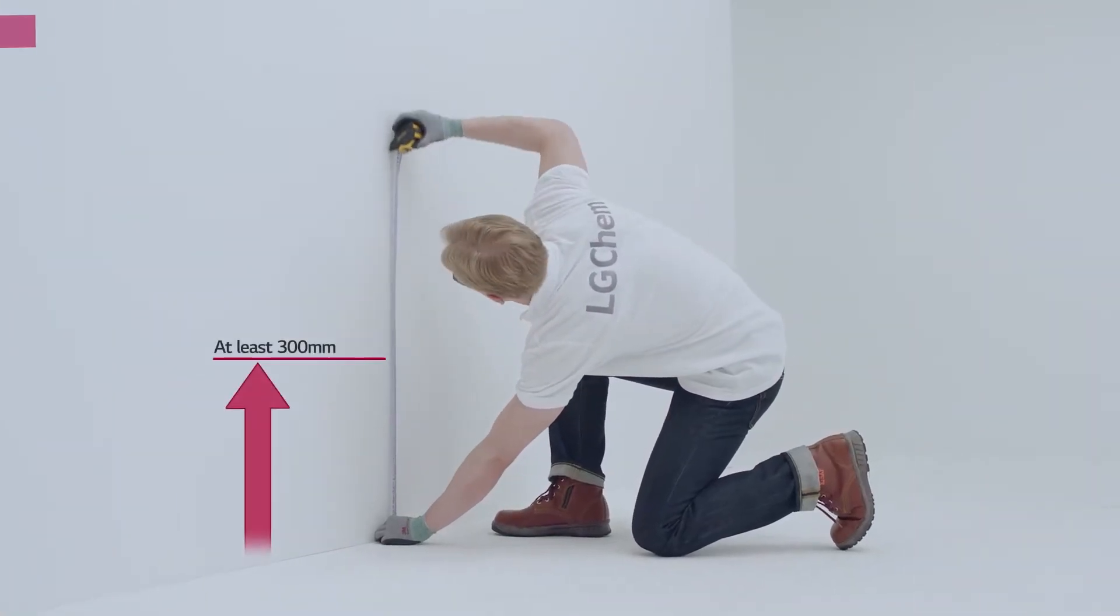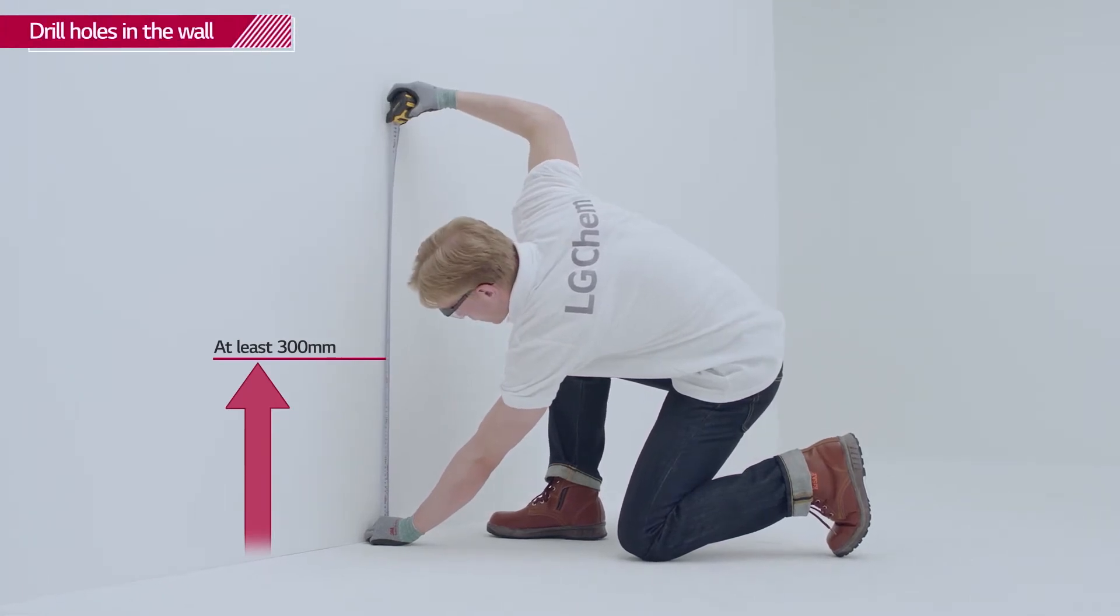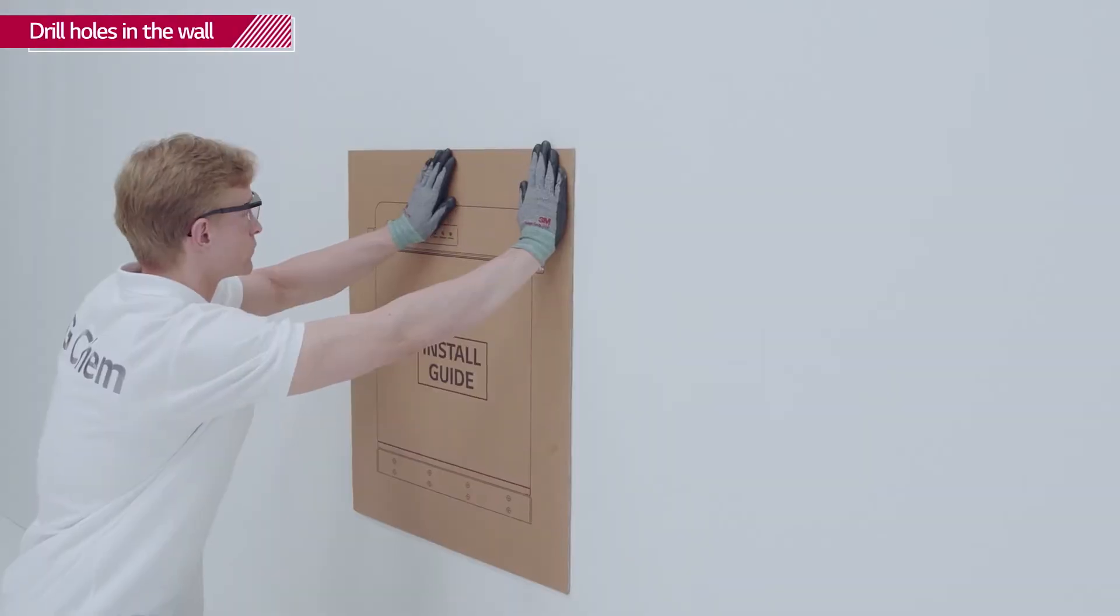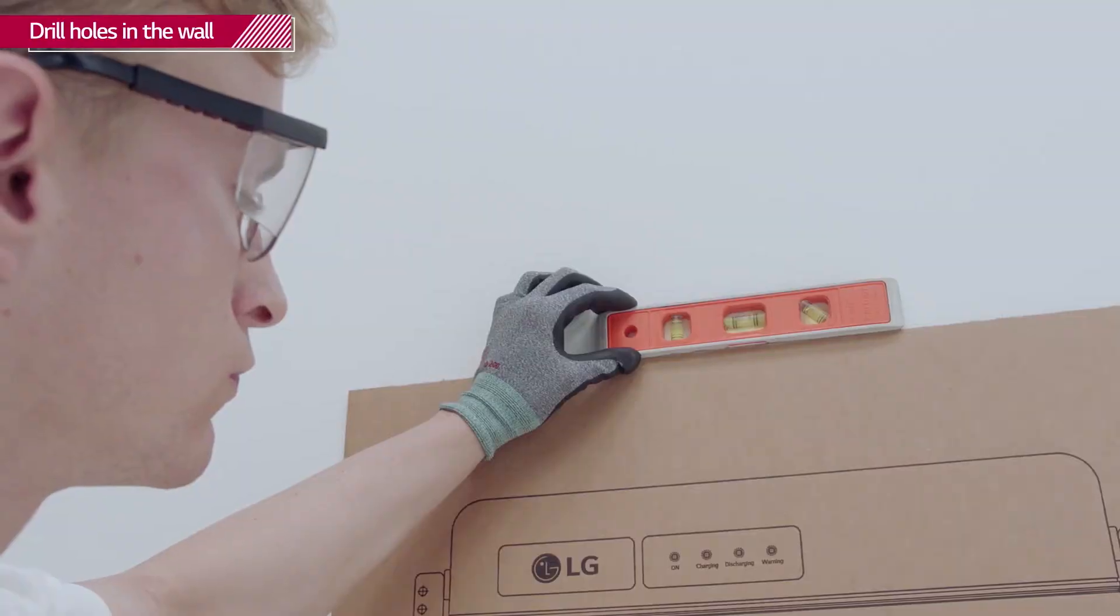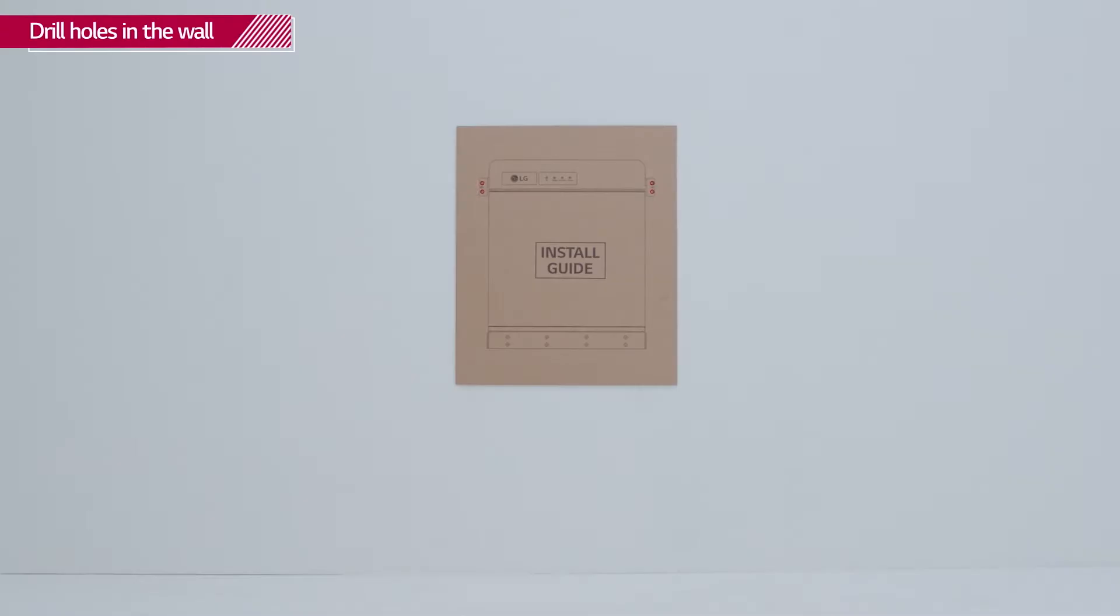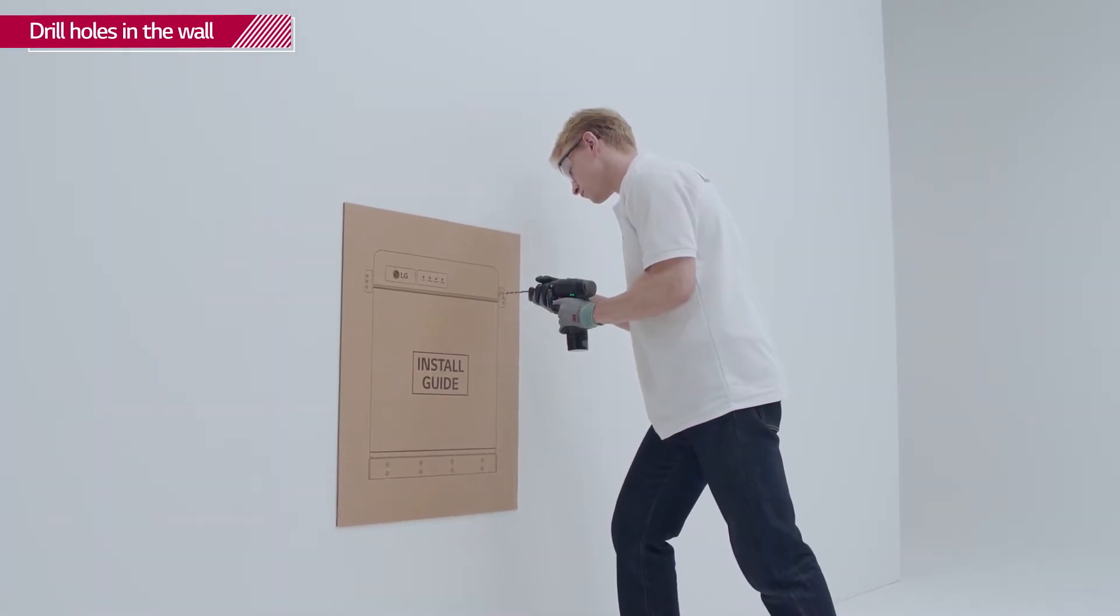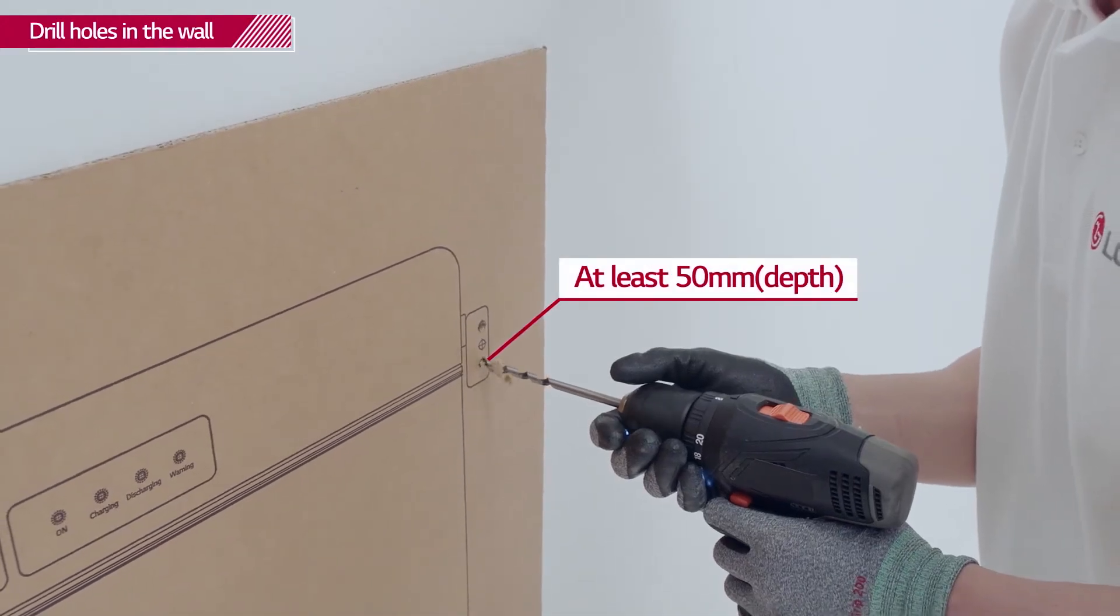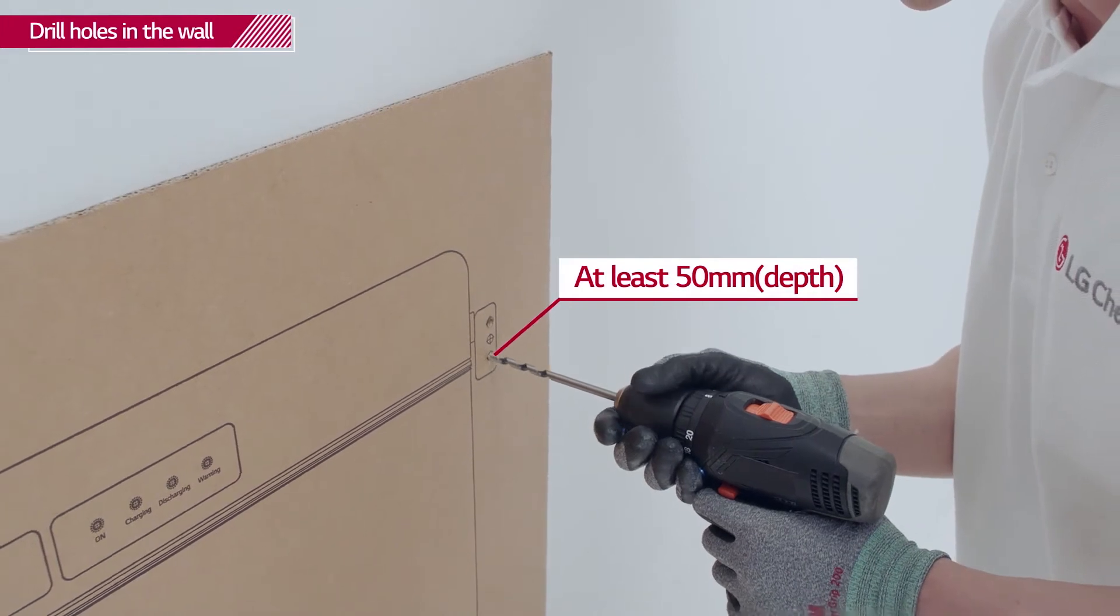First, check the height for installation. Attach the drill template to the wall and check that it is level. Drill four holes into the wall to fit the M6 screw anchors for the mounting brackets. The depth of the holes should be at least 50 mm each.